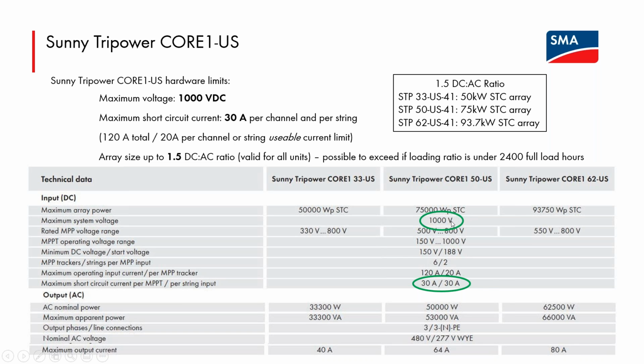If these values for the open circuit voltage and the short circuit current are always being respected, the first row of the data sheet shows the maximum array power, that is the maximum STC rating that SMA will allow you to connect to each model without any consultation from us. So if you do the math, it's a little easier for the 50 kilowatt unit. It's a 1.5 DC to AC ratio, or 150%. You may hear this referred to also as inverter loading ratio. There are a few acronyms for it across the industry. So that's a fairly good ratio, but we do get questions from folks who want to exceed that.